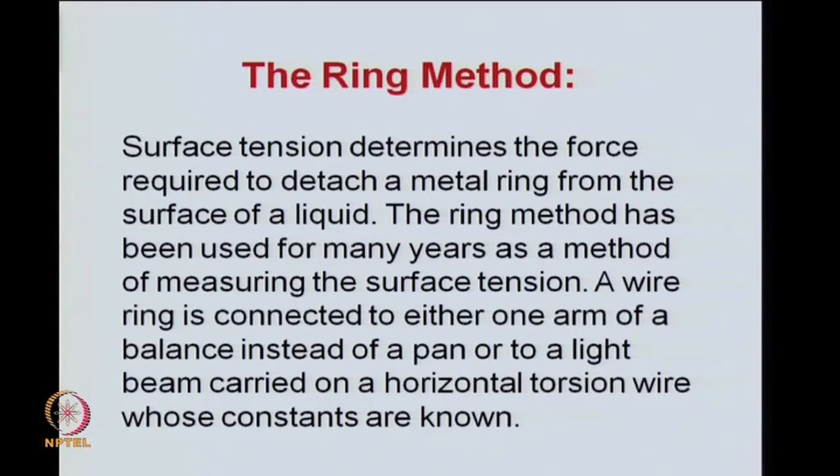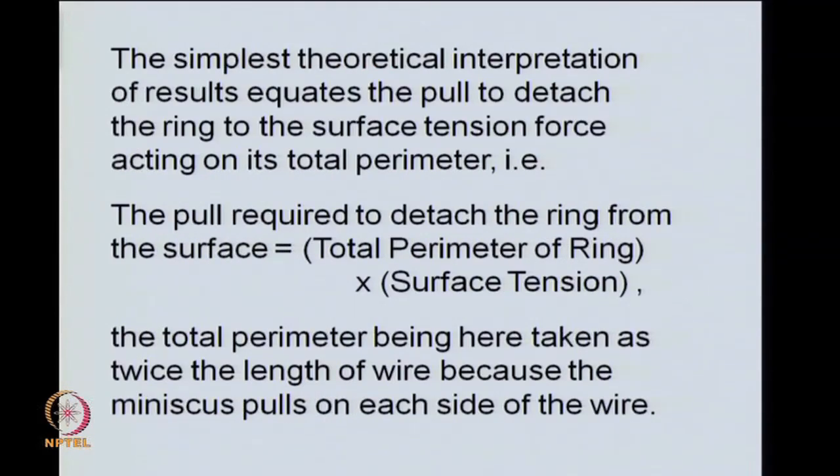Basically here you measure the force which is required to detach a metal ring from the surface of a liquid and is one of the oldest methods used for measurement of surface tension and interfacial tensions as well. A wire ring connected to either an arm of a balance or to a torsion wire through a light weight beam could facilitate the measurement of this vertical pull required to snap the ring off the liquid.